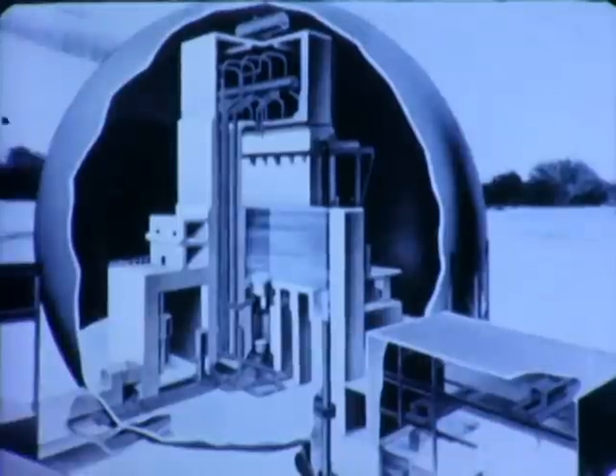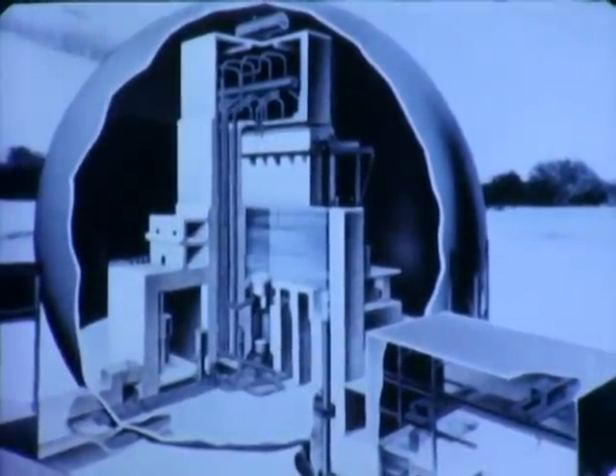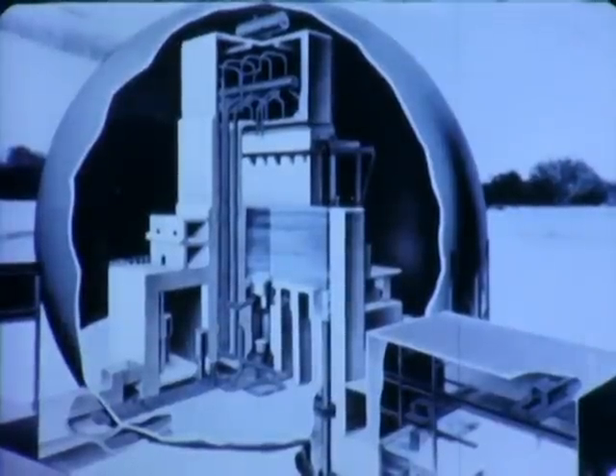The 350-ton pressure vessel is 40 feet high with an inner diameter of 12 feet 2 inches. Light water is used as both moderator and reflector. The 80 hydraulically driven bottom-entry control rods are cruciform-shaped stainless steel with 2% natural boron.